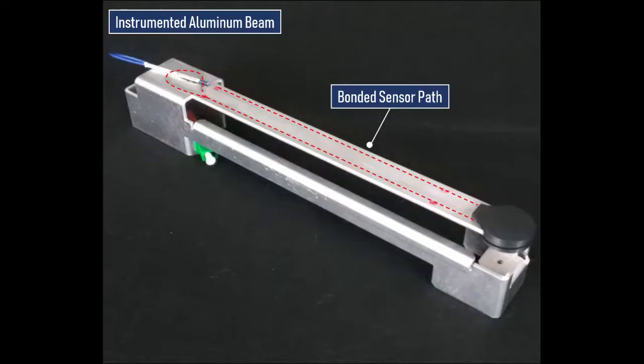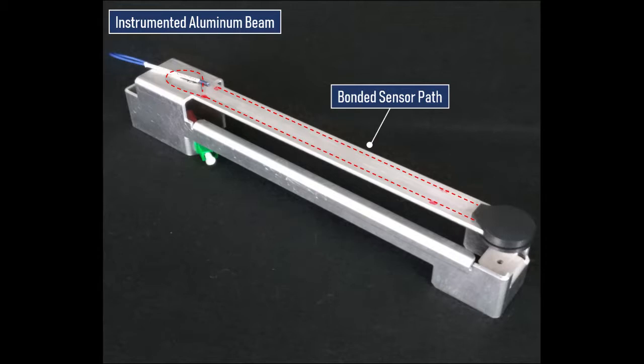For our test, we will be using a sensor that is already instrumented on an aluminum beam that can be flexed to make simple strain measurements. The sensor was bonded to the surface of the beam in the same way that a strain gauge would have been applied. The surface was sanded and cleaned, and then the fiber was bonded down using an epoxy.